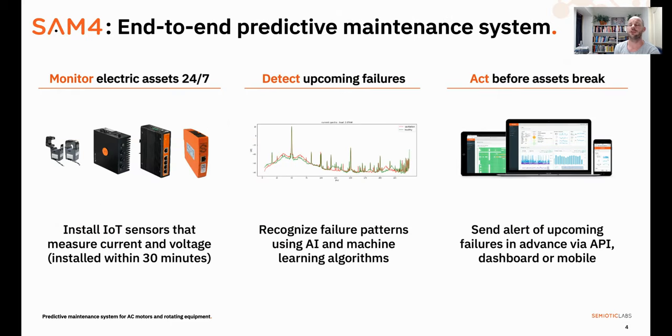Let's introduce SAM4. SAM4 is a predictive maintenance system for industrial electric motors and rotating equipment, including centrifugal pumps. It monitors those assets 24/7 to detect upcoming failures at an early stage, so you can schedule inspections, repairs, or replacements well before your assets fail. Looking a bit deeper into the technology, SAM4 consists of sensors that install inside the motor control cabinet where they generate electrical waveforms. Our data communication unit sends those waveforms to our platform where we initially start a 2–6 week learning phase after installation to create a baseline for healthy behaviors of that asset.